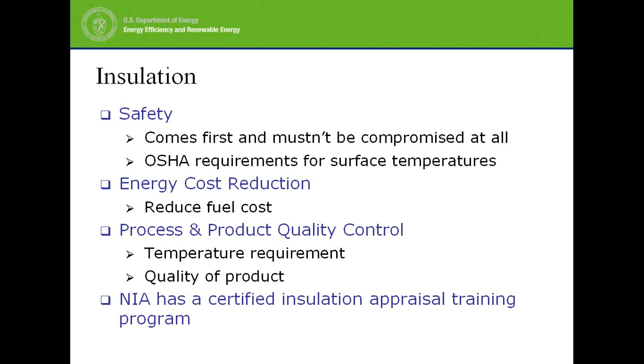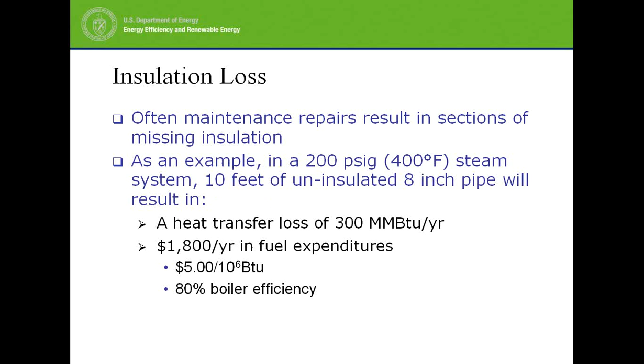Just a quick example: a 200-pound, 400 Fahrenheit steam system with a 10-foot uninsulated line on an 8-inch pipe, a very classic header configuration, could be losing about 300 million BTUs per year in year-round operation. At prices of about $5 per million BTU nowadays, with 80% boiler efficiency, that could be almost $1,800 to $2,000 a year in just energy cost. I'm not sure what it does to the process or production side, but that's why we're interested in it, mainly from an economic perspective.